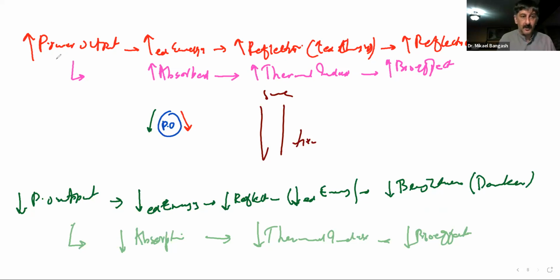At least for now, when we say power output, it means adjusting this power output knob, which may send out greater energy. If that greater energy hits a reflector or a tissue with whatever reflection intensity coefficient, it will reflect a certain percentage of that incident intensity back. If that was great, it will cause more energy to be received by the system and produce a bright reflection, or vice versa.